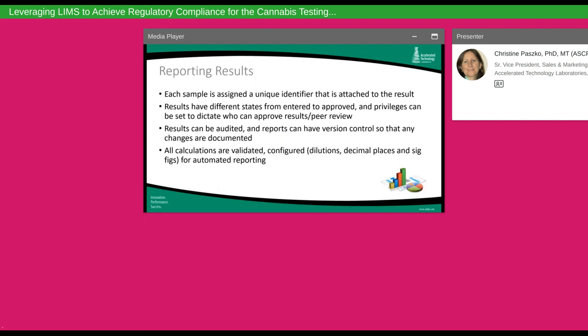For reporting results, each sample in the LIMS is assigned a unique identifier that cannot be reused within the system. Results have different states from when they're entered to when they're approved, with privileges set to dictate who can approve results — typically one person enters and validates a result, and a second person, often a supervisor, validates and approves it. Reports can have version control so data consumers know if a report is original or amended. Any calculations within the system can be verified, validated, and locked so they cannot be changed unless by the LIMS administrator. Final results can be configured for dilutions, decimal places, and significant figures.